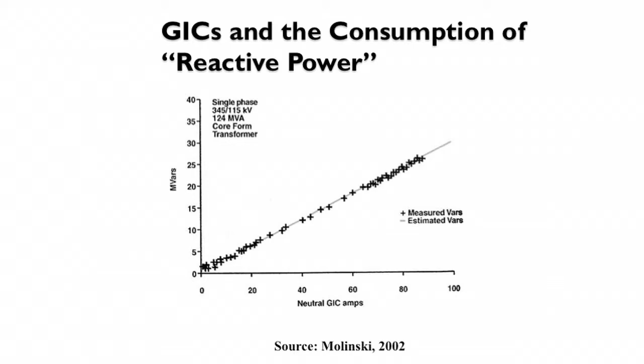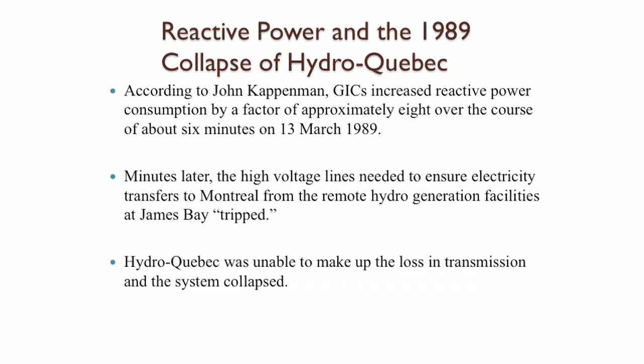John Kappenman has spent a lot of time studying this, and in the Hydro-Quebec collapse of 1989, he indicated that the GICs increased reactive power by a factor of approximately 8 over the course of about 6 minutes. Minutes later, the high voltage lines needed to deliver the electricity from the far north to the south tripped. There was an imbalance in the electricity - supply didn't equal demand anymore, and the system collapsed.